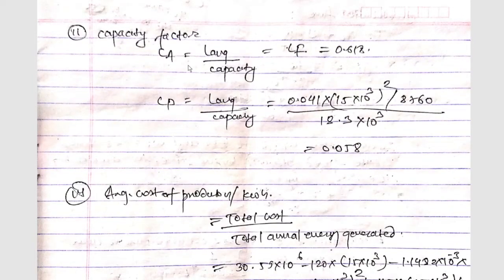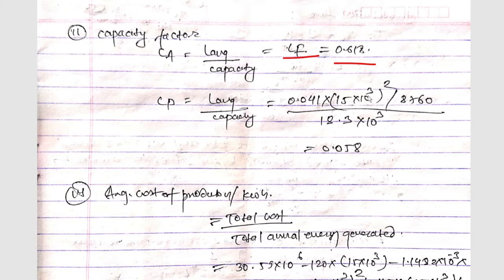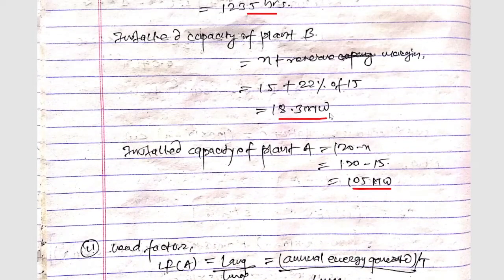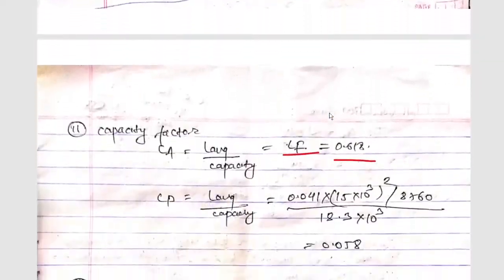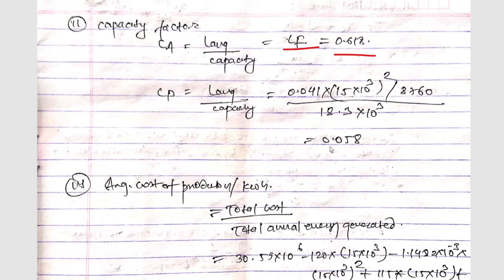For capacity factor, CA = L_average / installed capacity. For plant A this equals the load factor = 0.618. For plant B, capacity factor CB = 0.041X² (with X = 15 MW, converted to kW units) divided by 8760, over installed capacity 18.3 × 10³ kW, giving CB = 0.058.